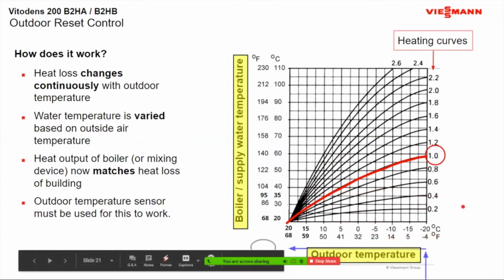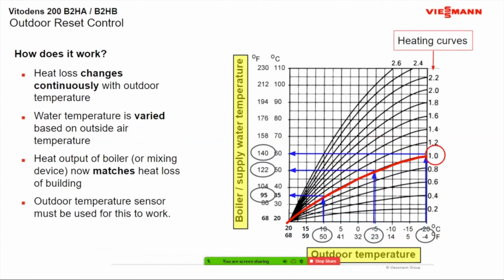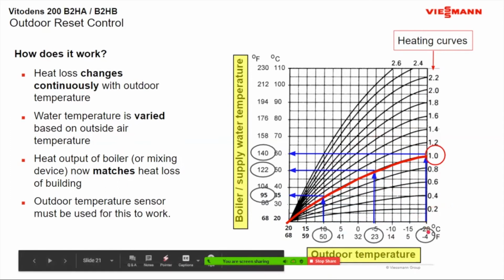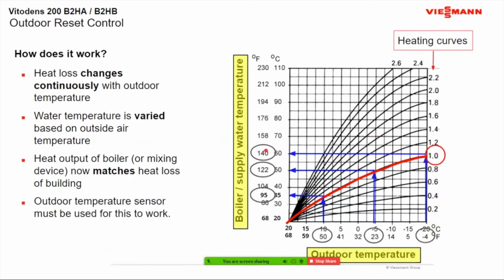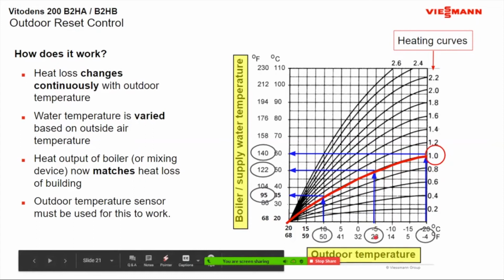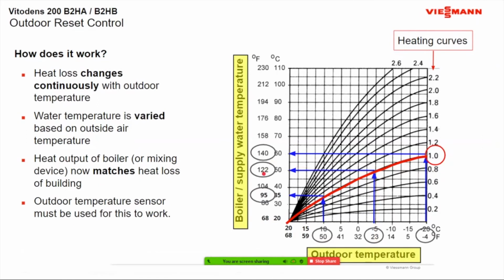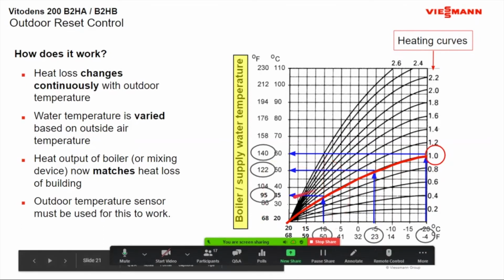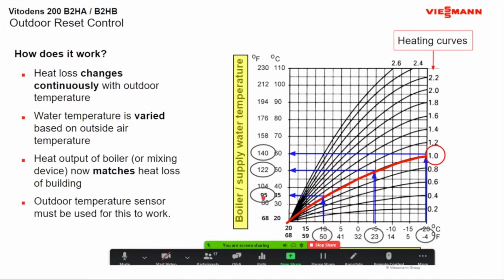So for this example, we just circled a couple of different outdoor temperatures. For this heating system, or it could be radiant as well, for a -4 day, we go up and follow that up to a 1.0, follow that line over through the chart. We're going to be heating that house with about 140 degree water temperature that day. Once the temperature starts to rise outside and we modulate up and down that scale, say it hits 23 degrees outside, we follow that up the scale, follow over, and now we're heating that house that day at 122 degrees. And so forth, at 50 degrees now we're heating the house at 95 degree boiler water temperature.